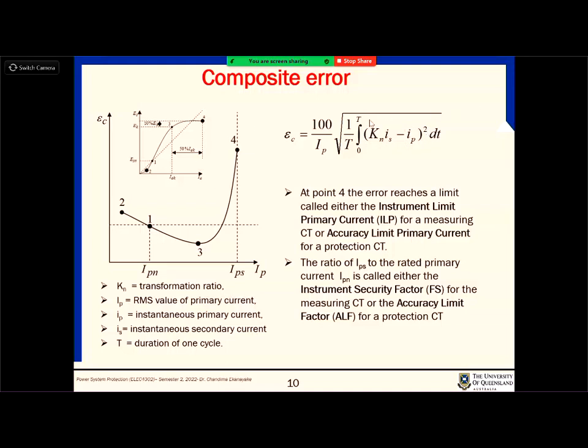And then we look at these instantaneous values, the simple IS and simple IP, which means they are instantaneous values. So if you have these instantaneous values, then you need to integrate it from 0 to t, and then take the square root of it and then divide by IP, which will give you the error ratio. If you multiply it by 100, then it is a percentage. So that's how you can find the error.